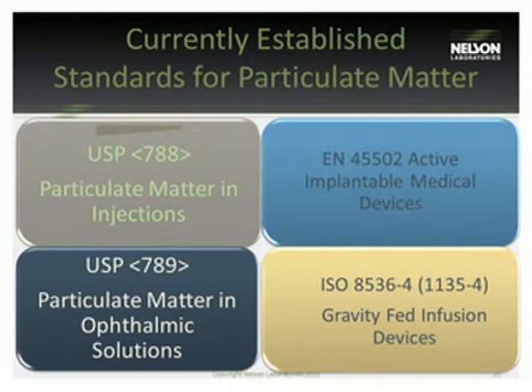EN 45502 is a standard specific to devices, but it's specific only to active implantable medical devices. Most of these will include pacemakers and different accessories that may go with those. We test very frequently to that standard, but again, it's specific only to those types of devices and not to others. So while it sometimes has been adopted to other devices, it's not usually recommended unless your device fits into that category. There are a couple other obscure ones. ISO 8536-4, harmonized with 1135-4, specific to gravity-fed infusion devices. Again, a very small niche of device.